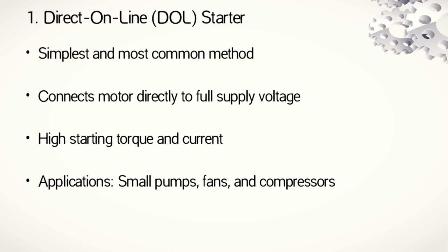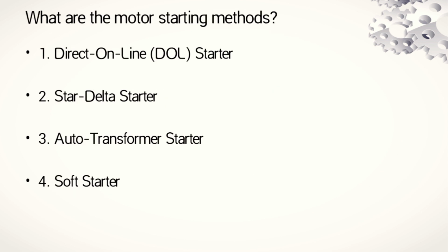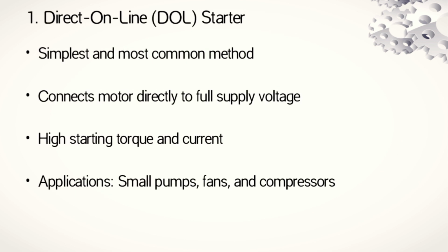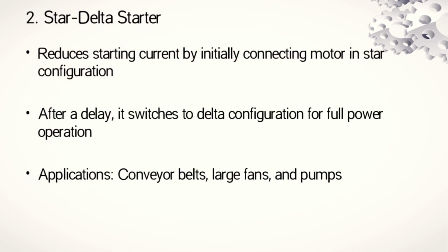So defining the types of motor starting methods, we'll start with the direct online starter, the DOL. The DOL is the simplest and the most common method of motor starting. It connects the motor directly to the supply voltage. High starting torque and current. So applications of the DOL starter: the first application is small pumps. The second is fans and compressors.